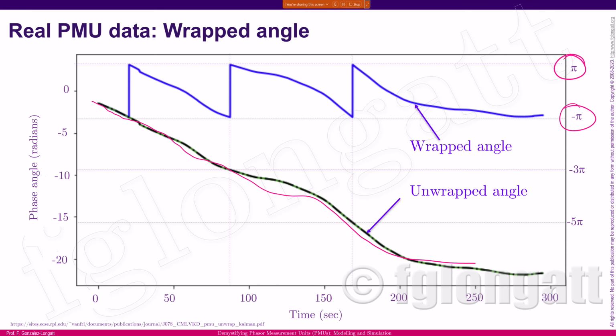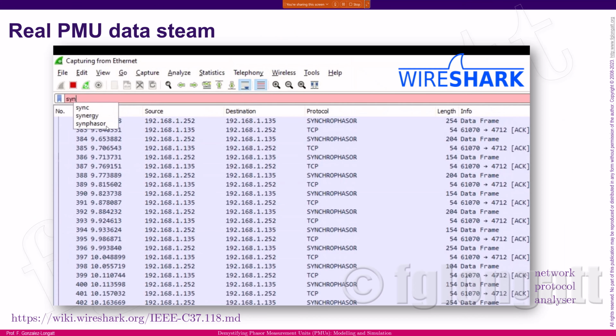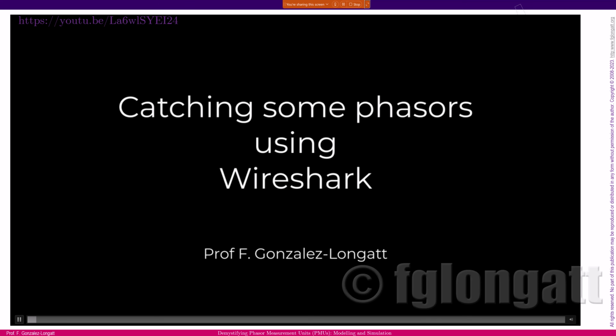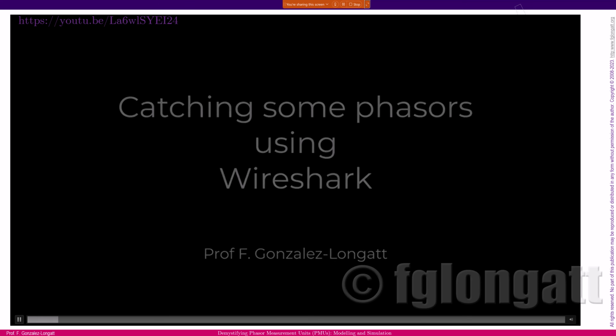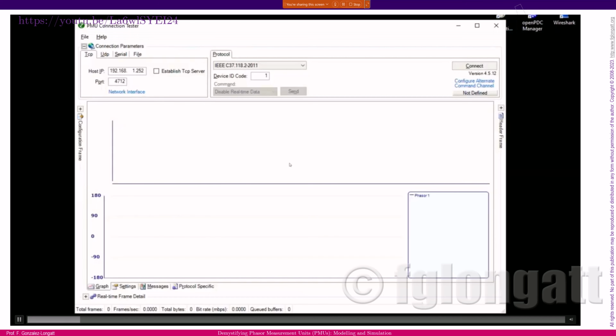Again, PMU data is very different from data obtained from an offline simulation. More than that, real PMU data comes in a data stream—produced in real time and sent over the local area network in real time, following the format specified by the IEEE C37.118 standard. Here, for instance, I can show you that we are using specialized software to capture this data.